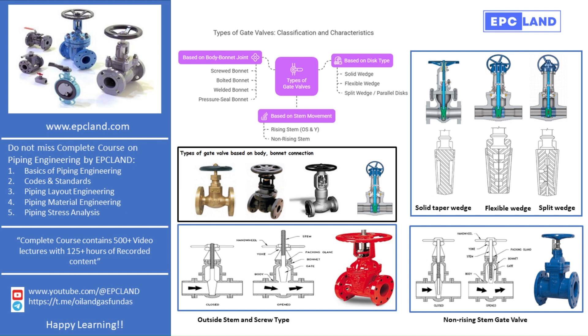Now we come to the third classification: types of stem movement. This classification is about how the valve stem moves when the valve is operated. The rising stem, or OS&Y type — which stands for outside stem and yoke — has the stem moving up when the valve is opened and down when closed. The threaded part of the stem is outside the fluid flow, which prevents it from getting corroded or damaged. You can easily know whether the valve is open or closed just by looking at the position of the stem.